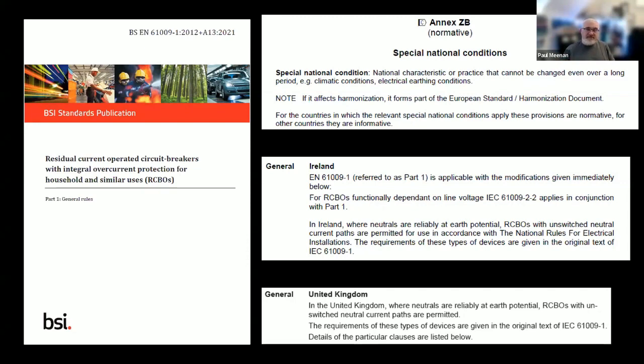But what if you don't have that? What if you have an installation where you have single pole devices and you have diverted neutrals and a rise in neutral current? Then surely you don't have a reliable earth potential there potentially. So it's worthwhile looking through your standards to see if there are any national conditions.